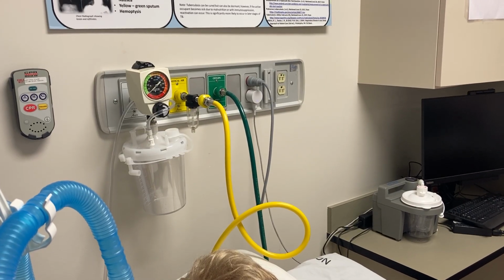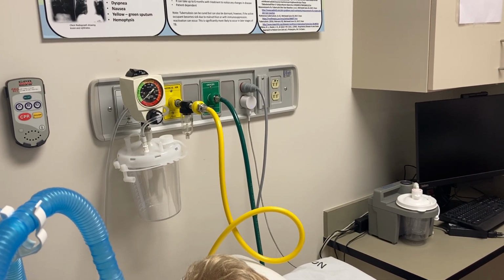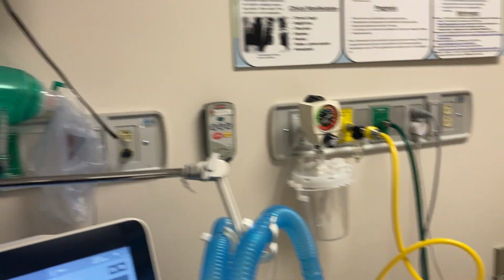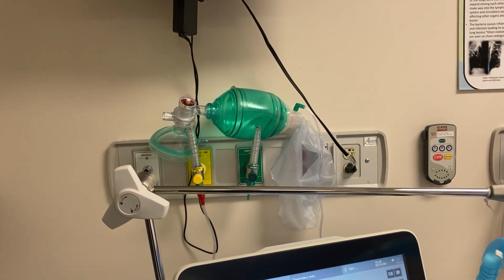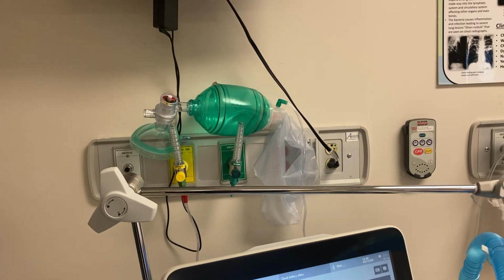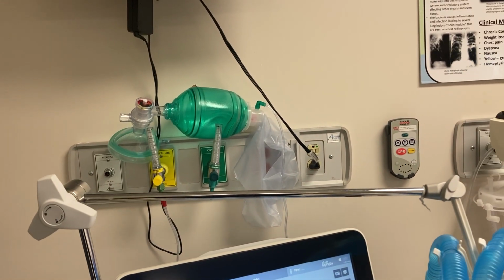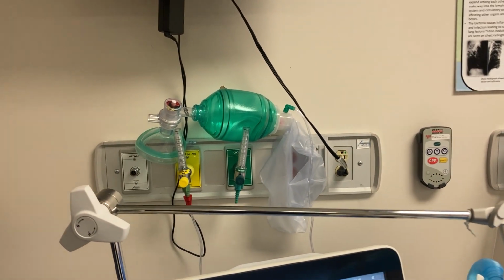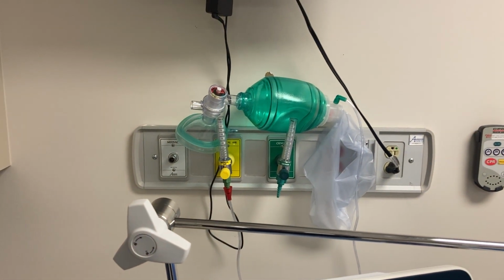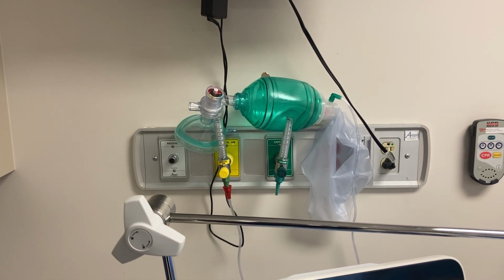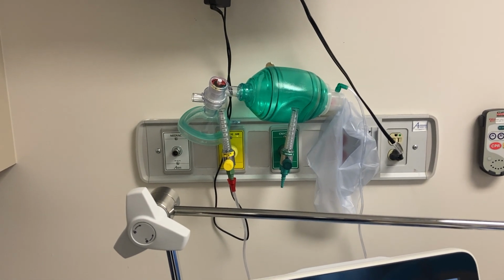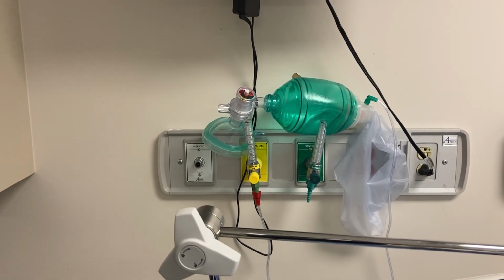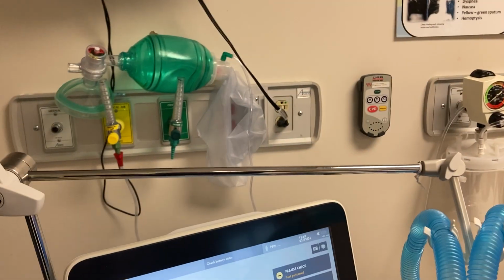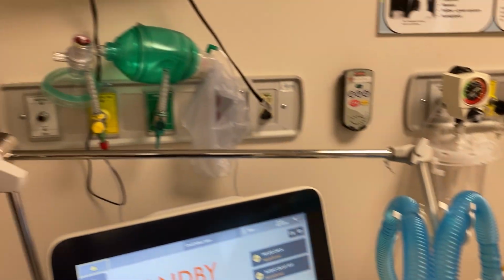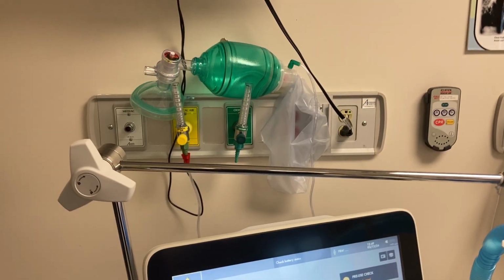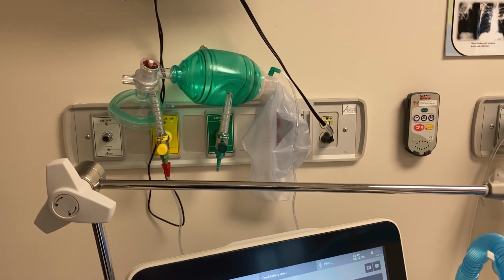So if we were to find that it was plugged in somewhere else, we want to make sure that we change that. And also we want to make sure that at a very minimum, we've got a bag valve mask or manual ventilation device with a mask attached to it. While we have one in the room, it is probably not advantageous that it is attached to the airflow meter. In the event of cardiopulmonary resuscitation or a code blue situation and we need to manually ventilate, it's possible someone just grabs that and begins manually ventilating with room air. We would like to ventilate with as close to 100% as we can. So that's something that we want to make sure that we pay attention to.